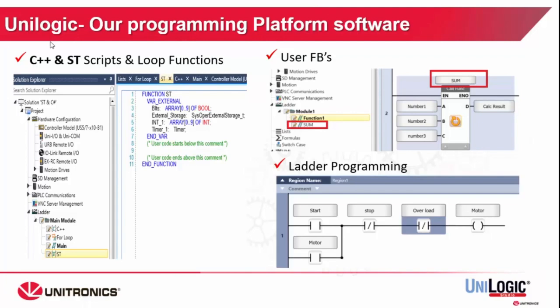UniLogic is our programming environment for our UniStream series controllers — completely free to use. It includes standard industrial ladder programming as well as the option to use C++ and structured text. You can combine these different languages all in one programming environment. For example, if you want a function built in C++ for mathematical operations or array handling, you can build that as a function and call it within your ladder programming.